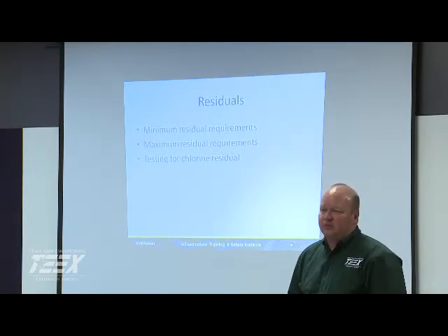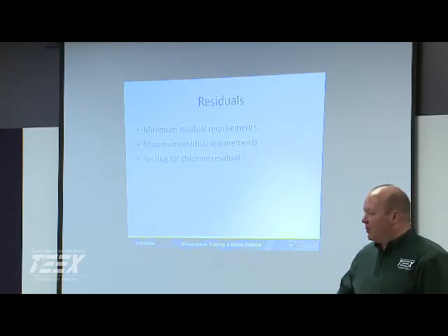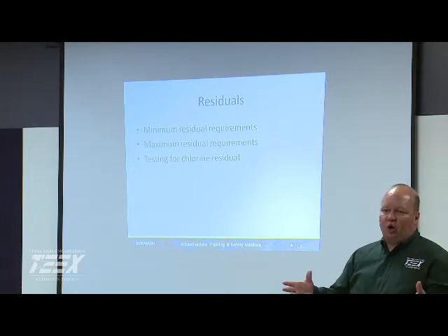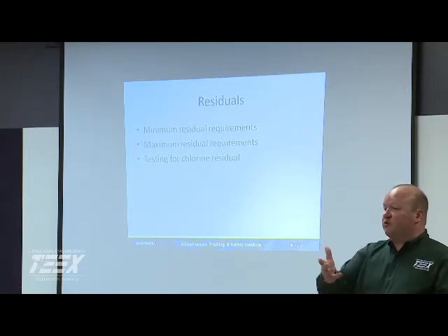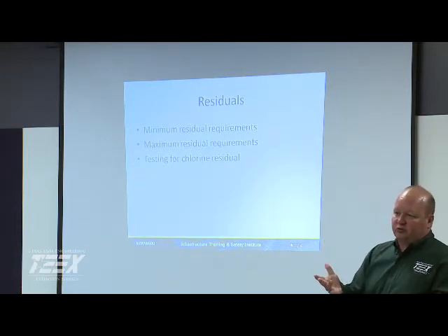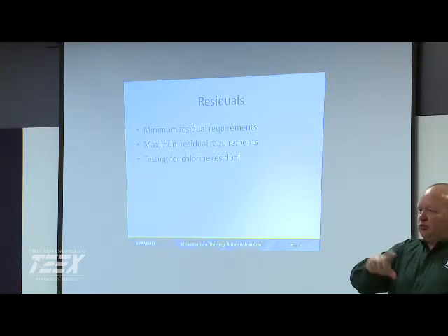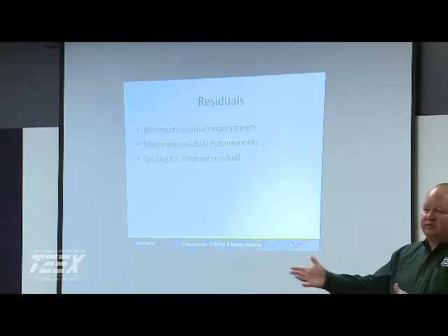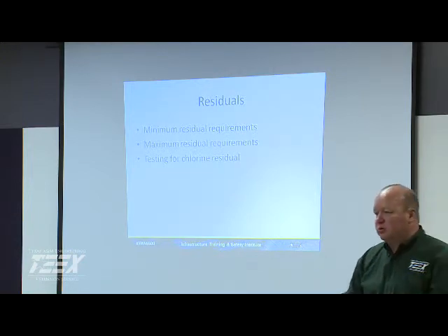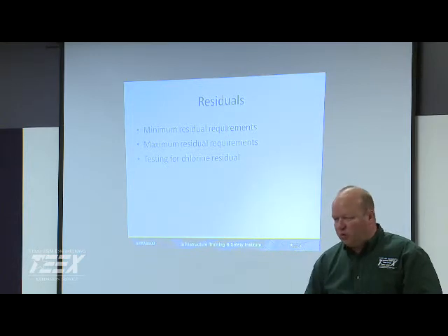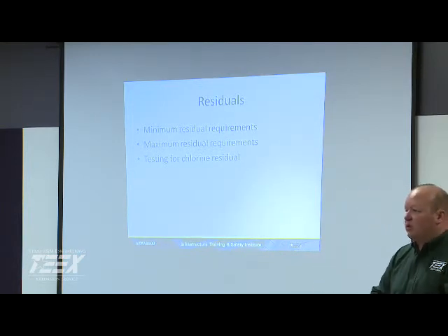Yeah, I'm a big proponent of a daily log or something like that, where even if you just have the secondary standards, and they'll last you 2 to 3 years, depending on when they send them out. Real easy to check, real easy to verify that it's at least within range. If you have something real goofy, you know you gotta do something else about it. So part of your quality assurance program, quality control, I'm a big proponent.